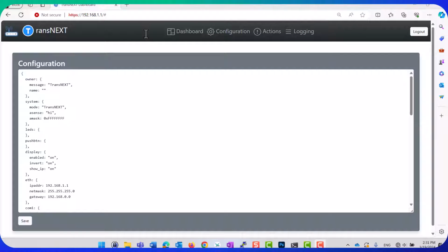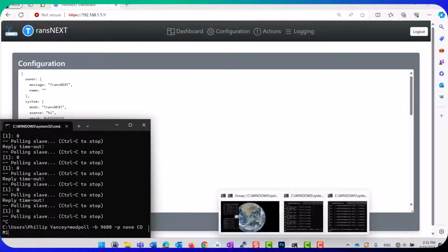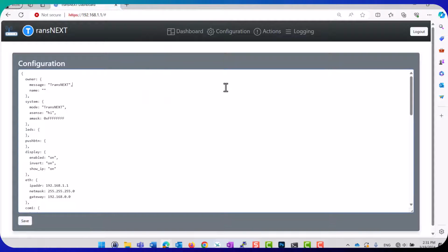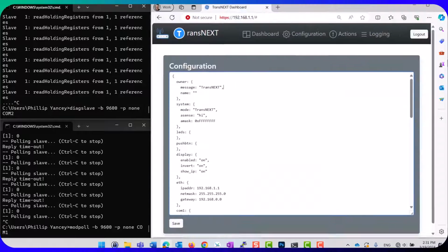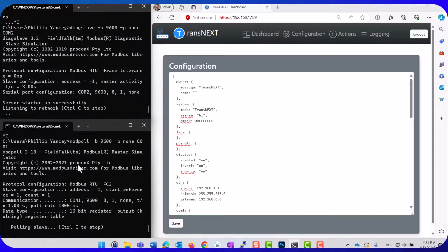Let's do some quick polling, just so you can see the proof of concept here. Right now I've just got a Modpoll device slave situation. We're polling 9600, 8N1, and I'm going to run my device and then run my poll. You can see here we've got a nice poll going.